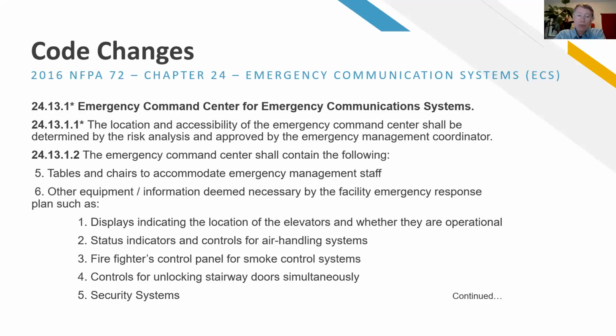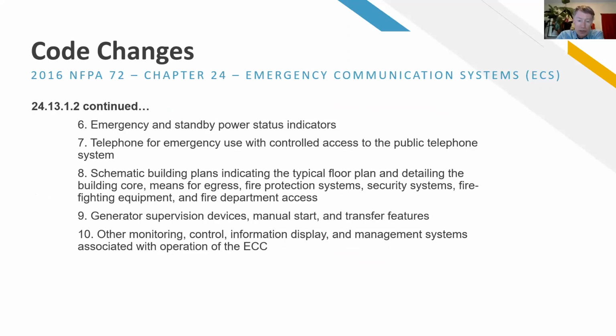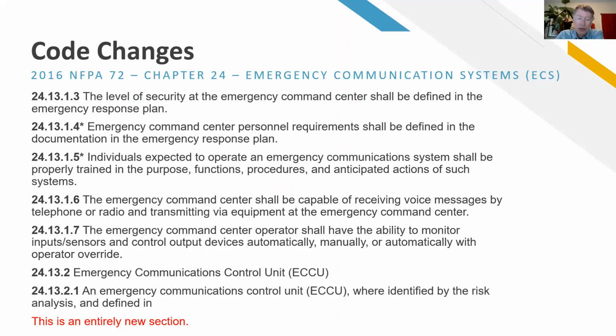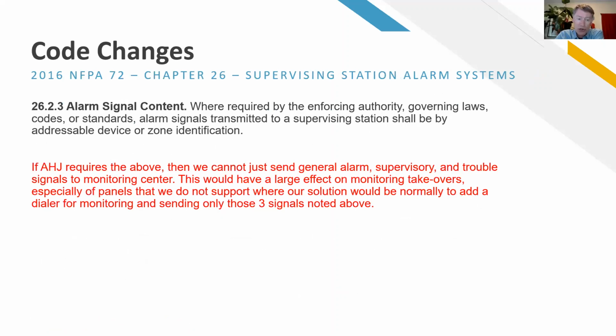And we are seeing, as designers, more and more applications for emergency communication by the fire alarm system. We do gas detection in medical device manufacturing or defense manufacturing, where gases can become toxic or explosive. So chemical leaks, violent intruders, all kinds of non-fire emergency communications can be delivered through a fire alarm system. The nice thing about a fire alarm system, as opposed to a PA system, is that the fire alarm system is supervised, so that if a wire gets cut, it monitors the integrity of the communication infrastructure. So you'll get a trouble at the panel and you'll know right away that, hey, somebody just took out this room or that wing. So we are seeing a lot more attention paid to fire alarm systems that do more than just evacuate occupants during a fire alarm condition. And that's a lot of the benefit for voice going into schools too, because we're seeing a lot more creative use to address emergencies that are non-fire alarm.